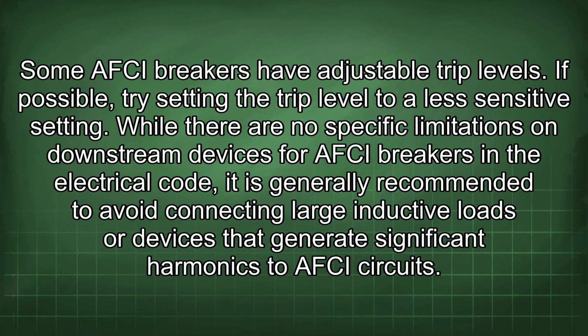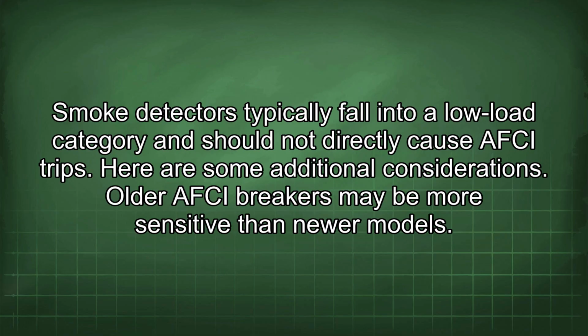While there are no specific limitations on downstream devices for AFCI breakers in the electrical code, it is generally recommended to avoid connecting large inductive loads or devices that generate significant harmonics to AFCI circuits. Smoke detectors typically fall into a low load category and should not directly cause AFCI trips.